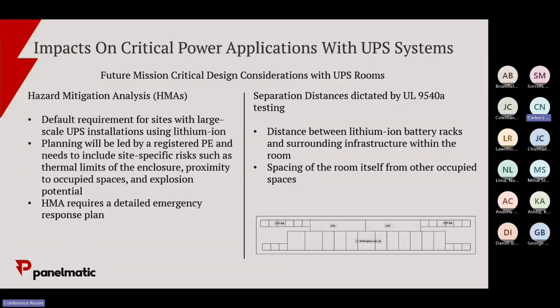But in this application, when you do it with other gear, the reason they require 3 feet is because in some large scale applications, you'll actually have to open the doors. If they detect a thermal runaway event or the VOC level gets above a certain threshold, they'll open all the doors to ventilate the room. Obviously, if you do that on a rainy day, now you have water going into your batteries - so probably not the best thing.